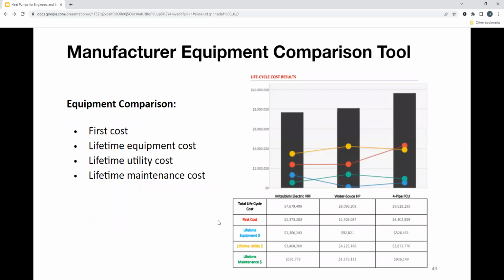And also, I like this table a lot. It has your 3 different options. So you have VRF right here, you have water source heat pumps, and then you have a 4-pipe fan coil system. And then it takes on the first cost, comparing that versus the lifetime expense of the equipment, right? Meaning lifetime costs, lifetime utility costs, and then also lifetime maintenance that's associated with that.